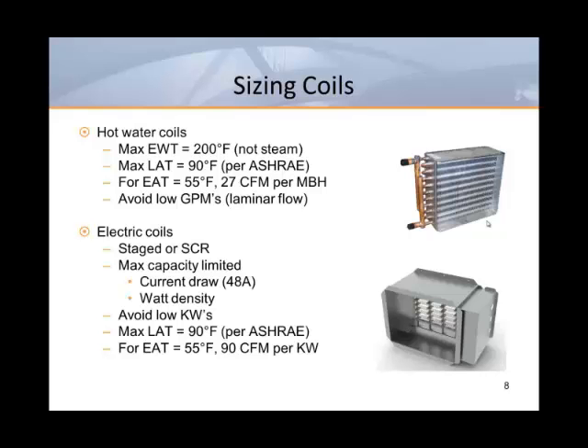This means that we should have at least 27 CFM per MBH to limit our discharge temperature. In hot water coils, it's important to avoid low water flow. If water moves too slowly through a coil, it can go from a desired turbulent flow to a less efficient laminar flow. It's much better to move water more quickly through a single row coil than to move it too slowly through a multi-row coil.